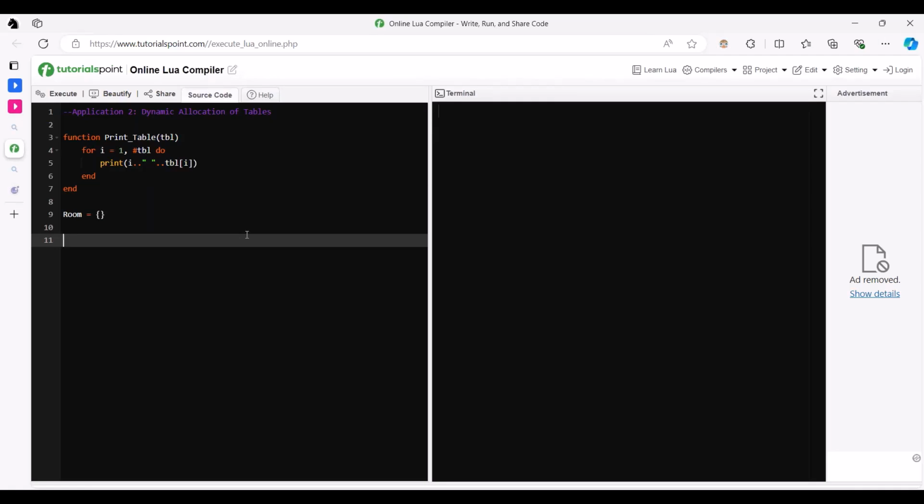So back on point, application two. We talked about the cap bank logic that we wrote for keeping track of volt-VAR optimization for one of our customers. The idea was a certain number of feeders had access to certain cap banks at different times, and that could change dynamically throughout the day. The user could go in and say, I want cap bank 5 to be operated by something else, a different feeder had control over it. So that would switch back and forth. And to do that, you need to be able to allocate assets in your tables dynamically.